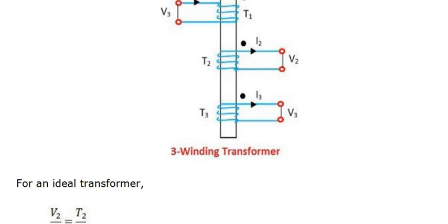Fourth one is a delta connected tertiary reduces the impedance offered to the zero sequence current to allow sufficient earth fault current for proper operation of protective devices. Tertiary winding can be used for measuring voltage of high voltage testing transformer. And next reason, supply a single load from two sources where the continuity of supply is important.